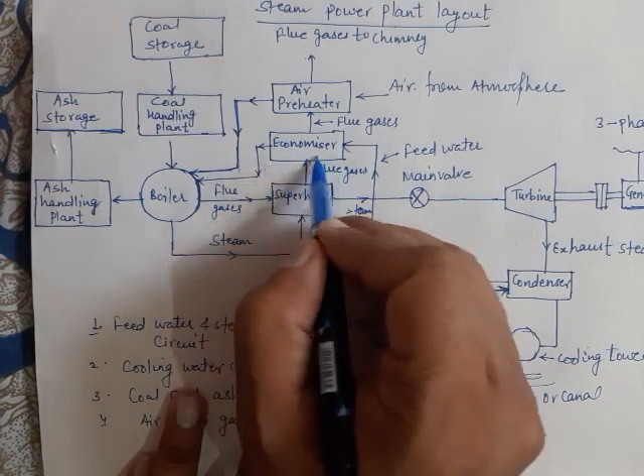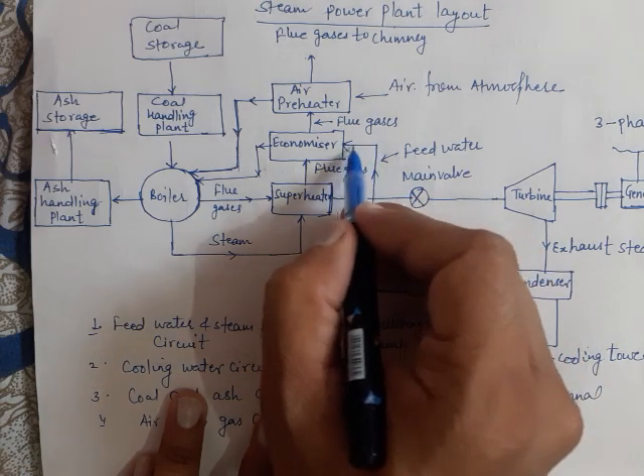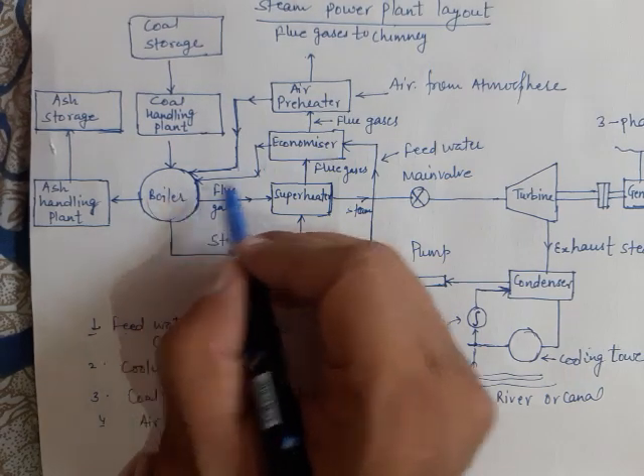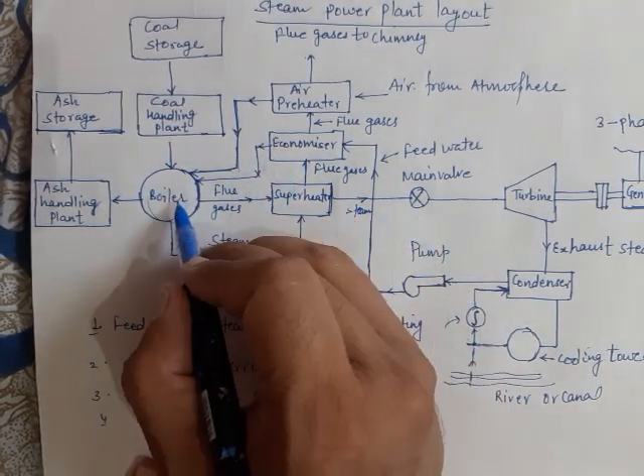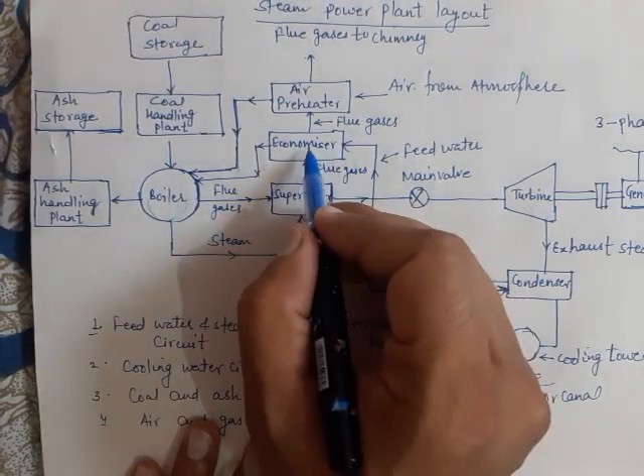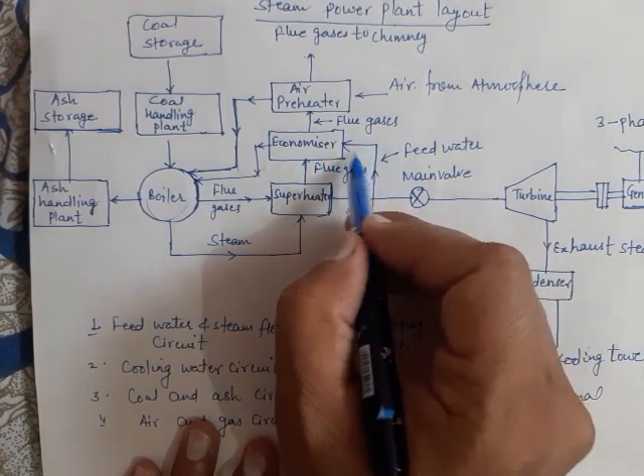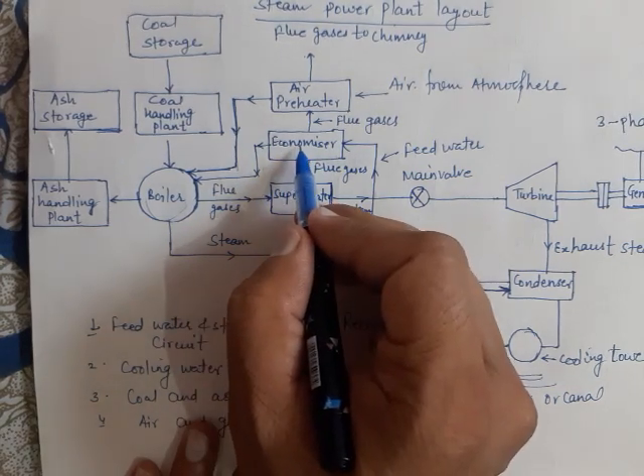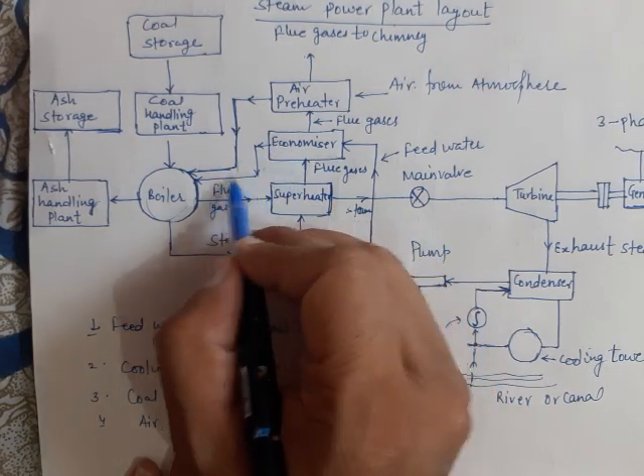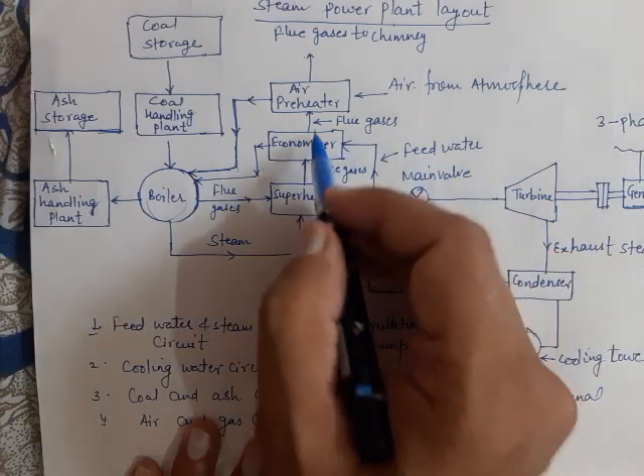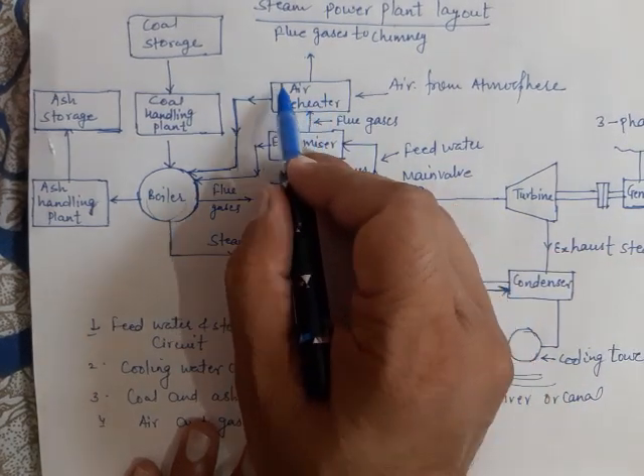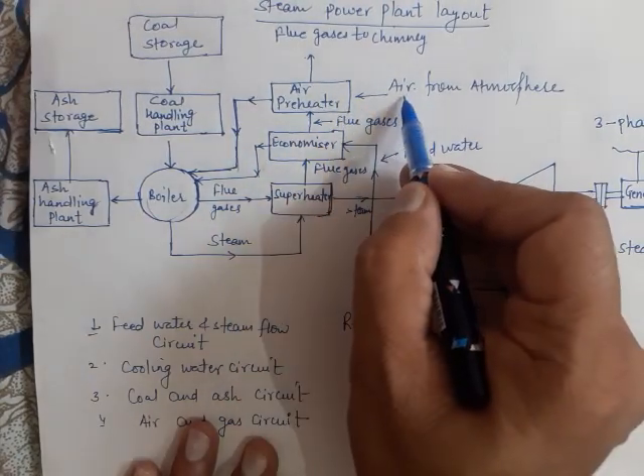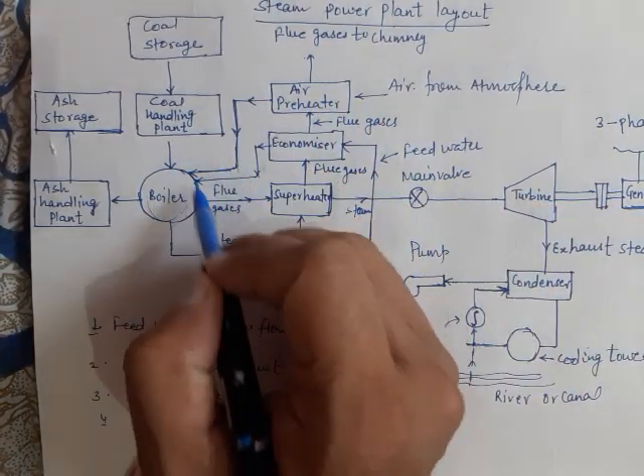After the superheater, the flue gases flow through the economizer, where their waste heat is utilized by the feed water. The economizer acts as a water preheater — the feed water is preheated inside the economizer using the waste heat of the flue gases, and then sent to the boiler. After that, the flue gases flow through the air preheater, where the incoming air is preheated.